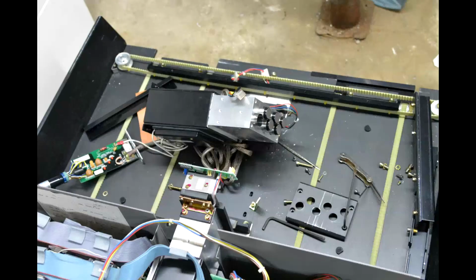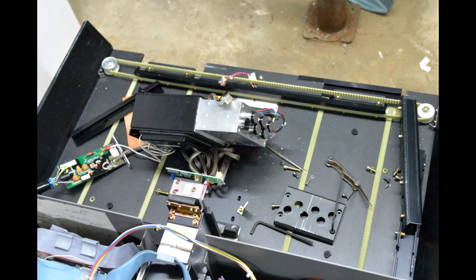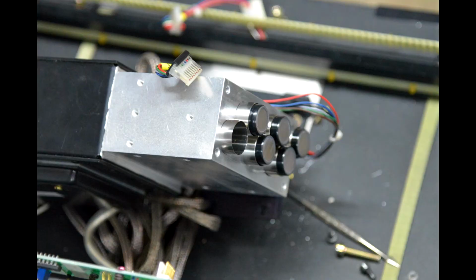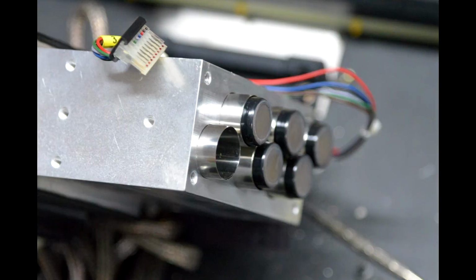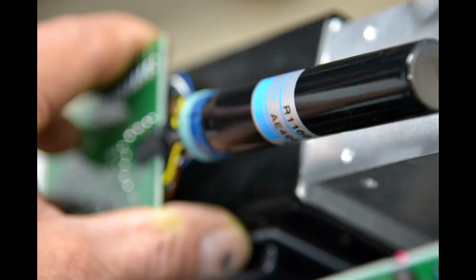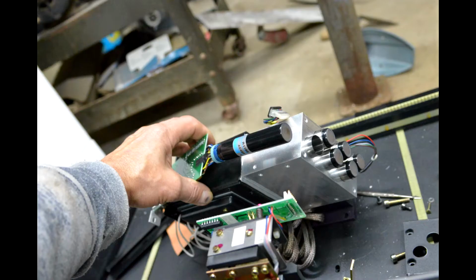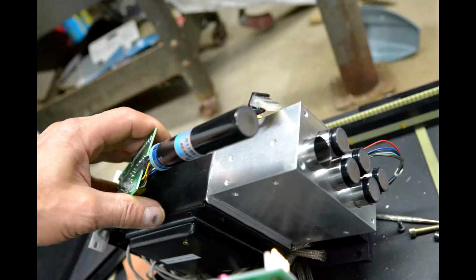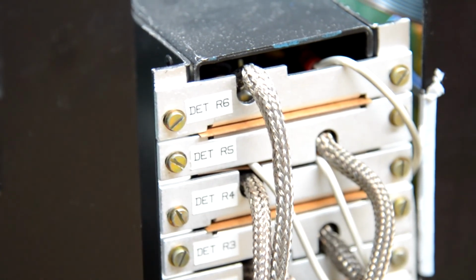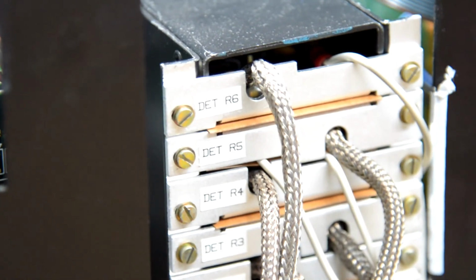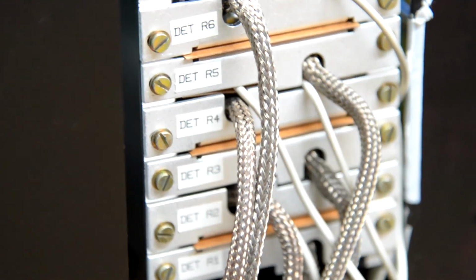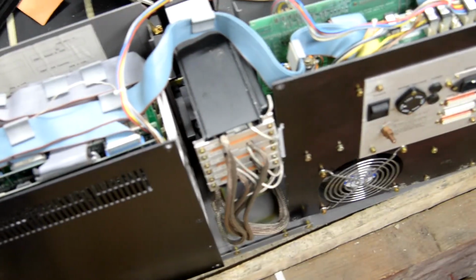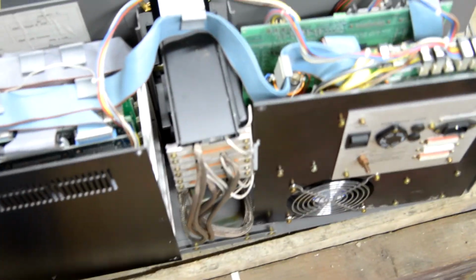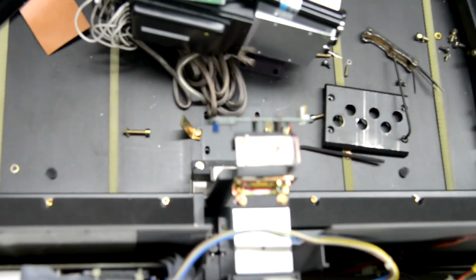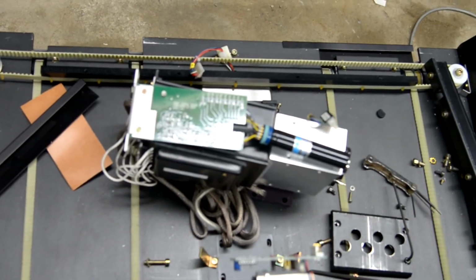Manufacturers use a stack of photomultipliers, 6 in one stack, 6 in the second one, and each one of the photomultipliers has its own power supply and preamplifier. That is done for the reason that when they have a pallet with the micro drop cells, each one is supposed to be independently screened in the light seal enclosure, so there is no need for screwing the screws around the cell. It is simply a flow of those cartridges, and the result is displayed on the screen.